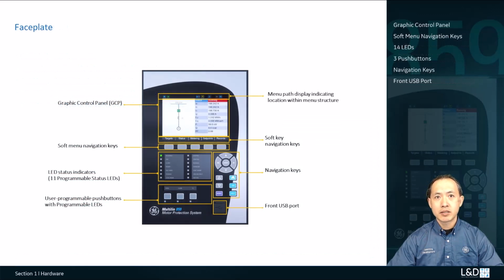859 faceplate is the same as all the other 8 Series relays. It has a big LCD display of graphic control panel. The single line diagram and the parameters are also shown on this screen. There are 5 navigation push buttons, which can navigate the menu according to the menu tab associated with the push buttons. Below the soft menu navigation keys, there are 14 LEDs, 11 of them programmable. There are 3 programmable push buttons and LEDs below. On the right side, the navigation keys include the arrow keys, escape key, enter key, help key, and reset key. The reset key is used to reset a trip or latched alarm. Below these keys, there's one USB port for quick connection with the Vista software.